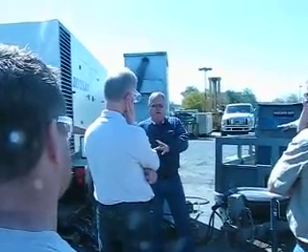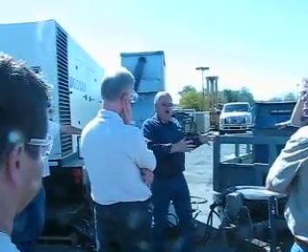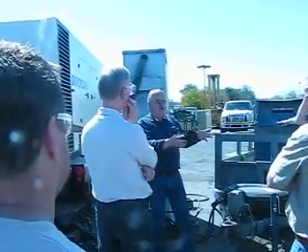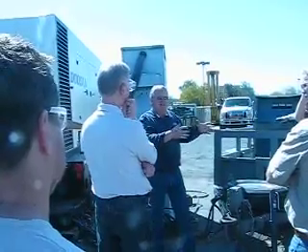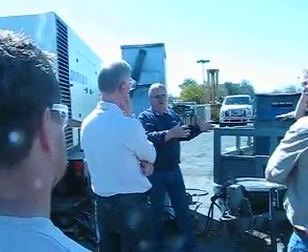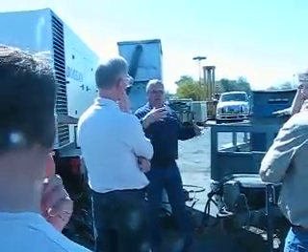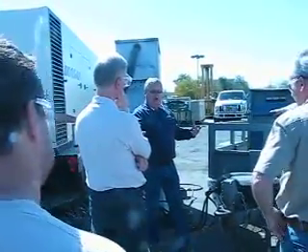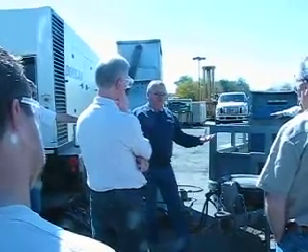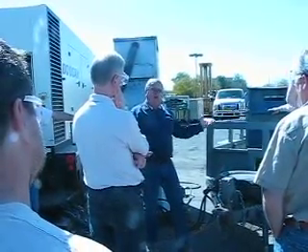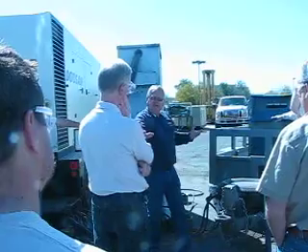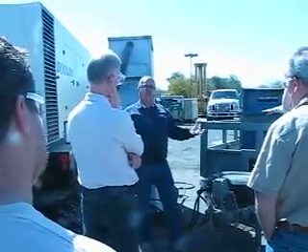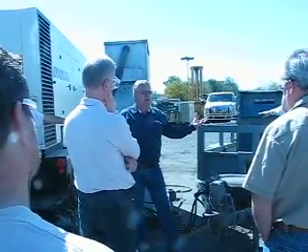It's doing the work. Now, what about kVARs, amps? What's controlling that? Alternator. Alternator, but more specifically, the magnetic field. The voltage regulator is controlling that. The governor to the engine is controlling the work, the KW. The voltage regulator is to the alternator what the governor is to the engine, okay? The regulator is controlling, in a paralleling application, the amps, the kVARs, okay?